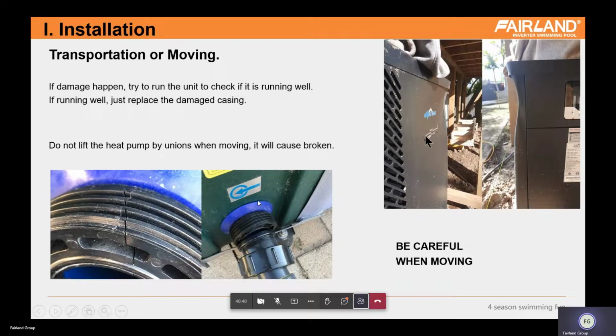And sometimes the customer will suffer a problem, because the unit is a little heavy. So when they lift the machine, they will grab the water union here. That will make the water union crack like this. So don't move the heat pump by grabbing the unions. Otherwise, the whole unit needs to be replaced, because the titanium heat exchanger needs to be replaced completely. That's a big job. So just be careful on this part.